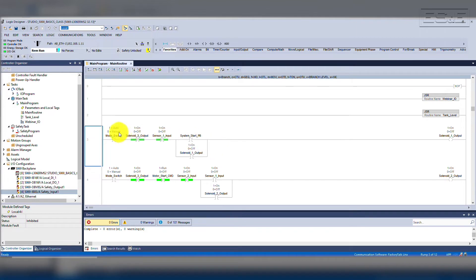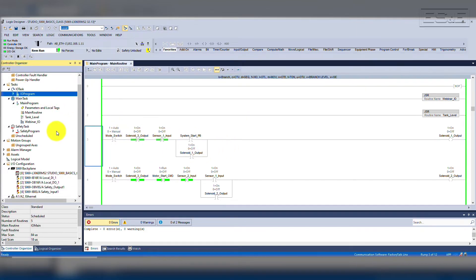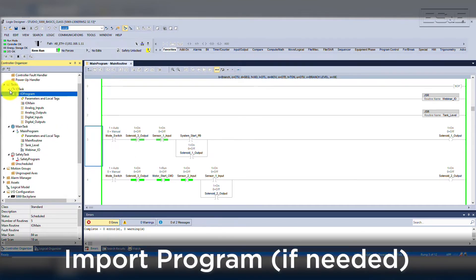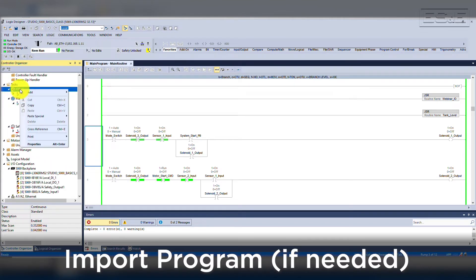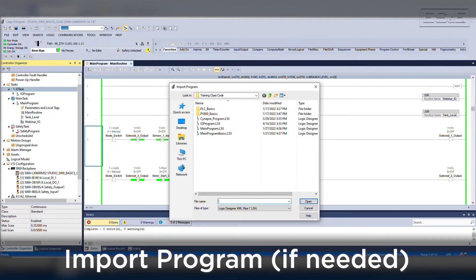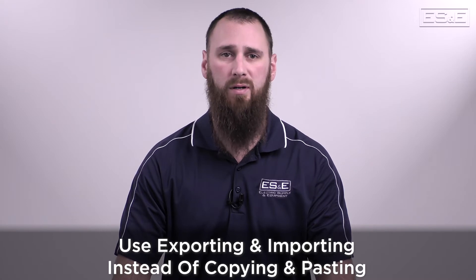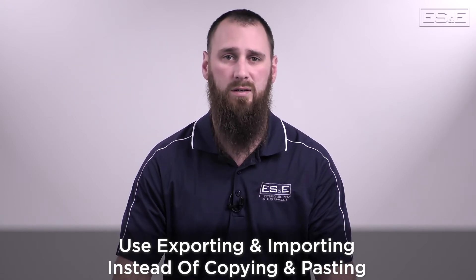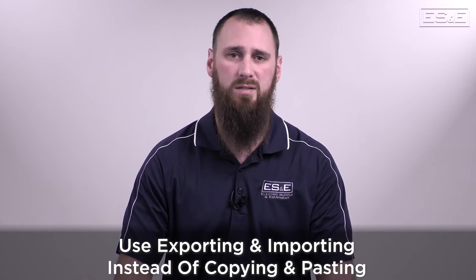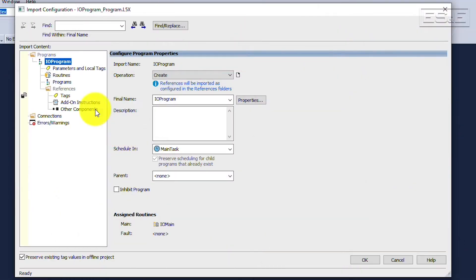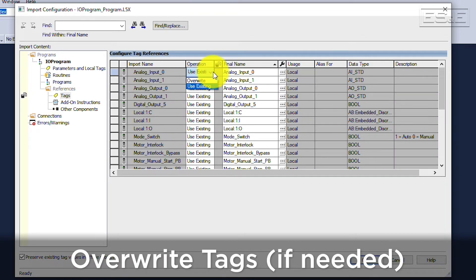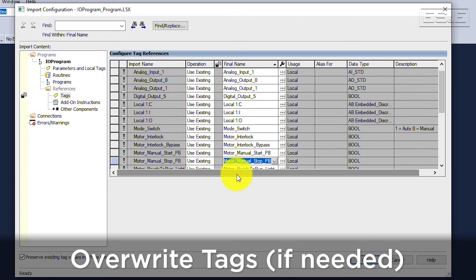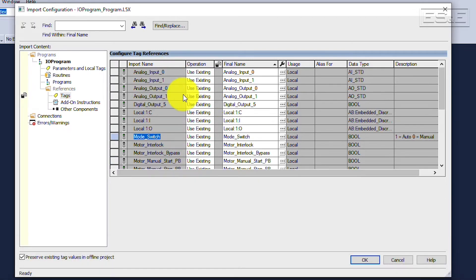Inside the controller under the task folder, the first task is called IO Task. The task currently doesn't have a program, so instead of creating a new program, we will import a program. We will browse for IO Program and then select Open. Importing has the ability to create all of the tags in Logic for you. This is one major reason why it is best to export and import instead of simply copying and pasting code. You can export and import add-on instructions, routines, programs, and projects. When importing, you can see all the tags, routines, and add-on instructions needed. If there is an error or existing tags, it will ask if you want to overwrite the tags, indicated by a red triangle on the folder. If you copy and paste, that requires you to manually create everything needed on your own.